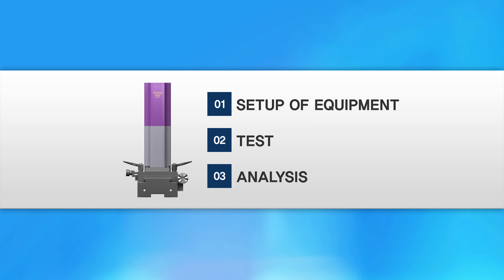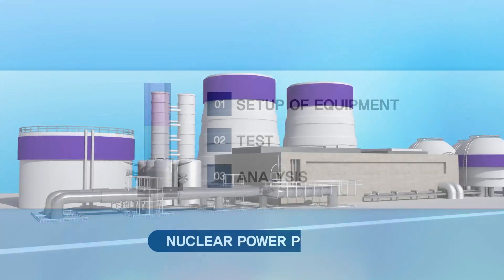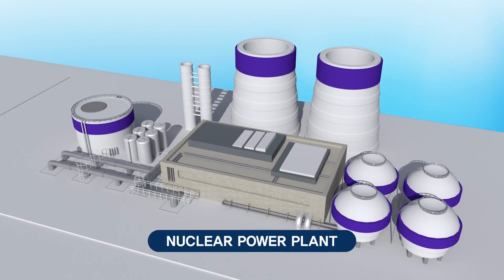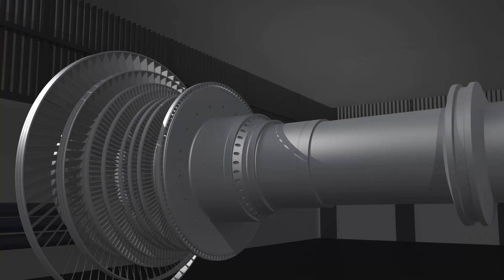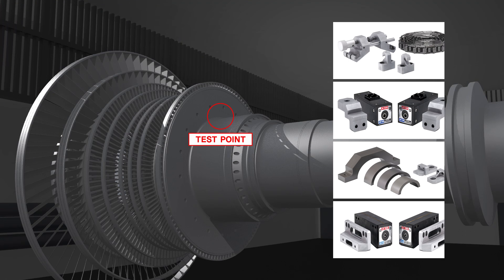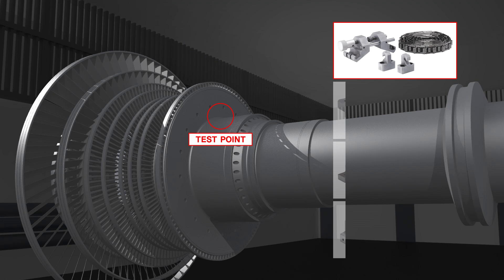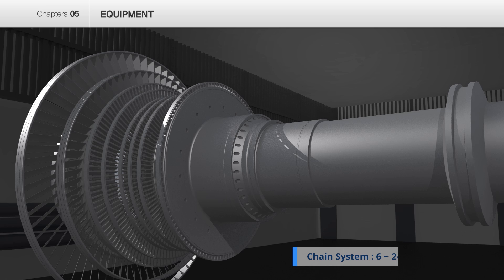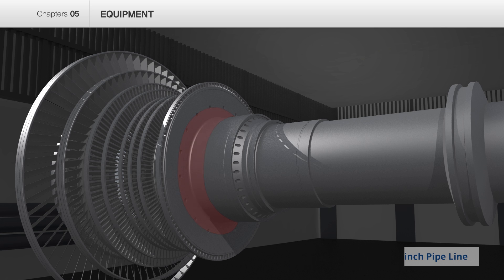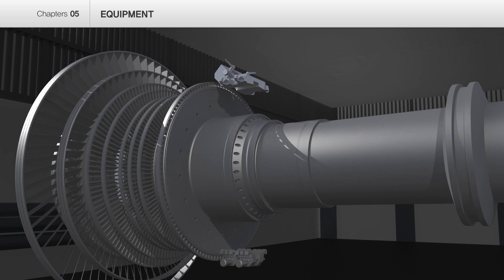Test procedure is like this. When the test position is determined, polish that area with automatic polisher, and then select the proper attachment to fasten IIT onto the object for non-destructive testing. These processes can be done in 5 minutes. In this video, it is using chain system as attachment to tested pipe.